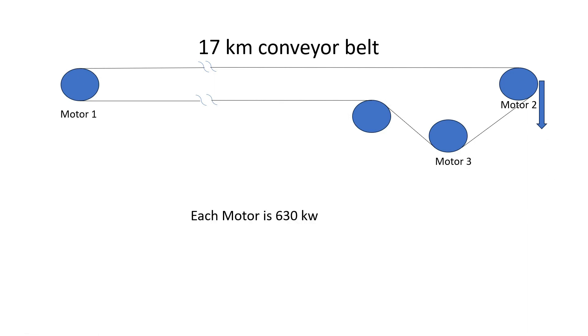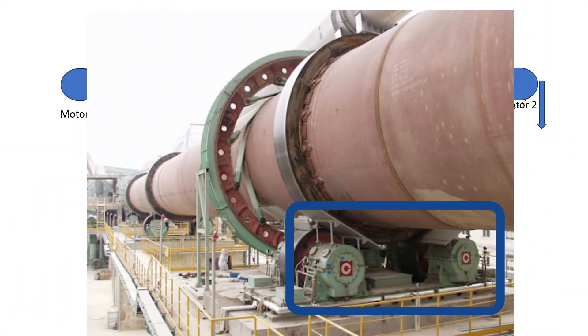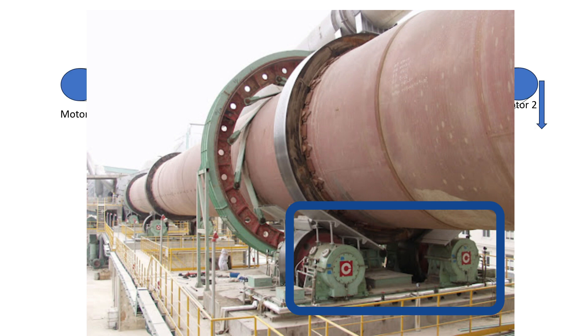There is a function named Master-Follower. The Master-Follower function is used in drives when equipment like a conveyor belt is run by two or three motors, which can be flexibly or rigidly coupled. If your equipment is rigidly connected and driven by two motors, you have to use Master-Follower in torque control mode to share the load perfectly. Otherwise, your equipment will break.